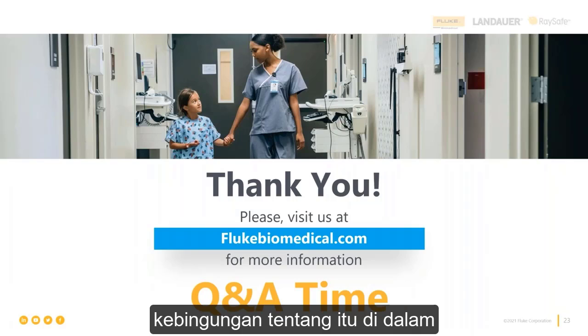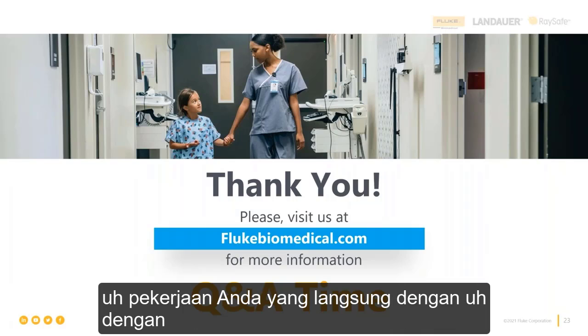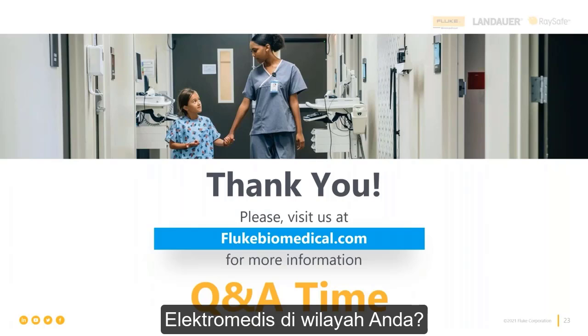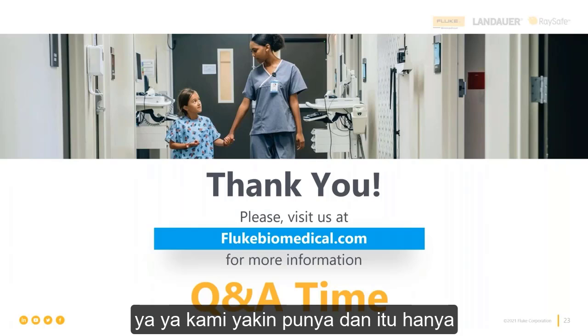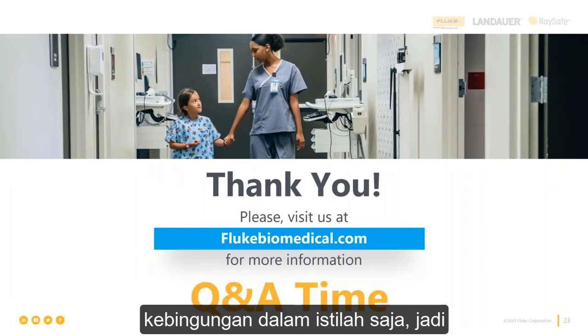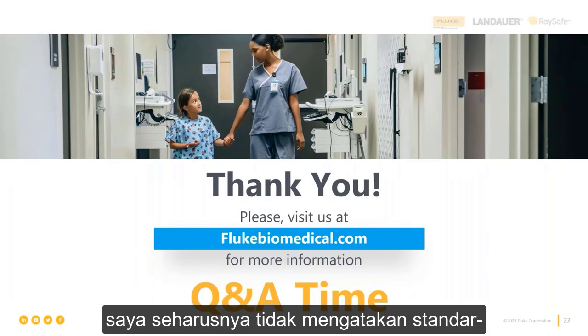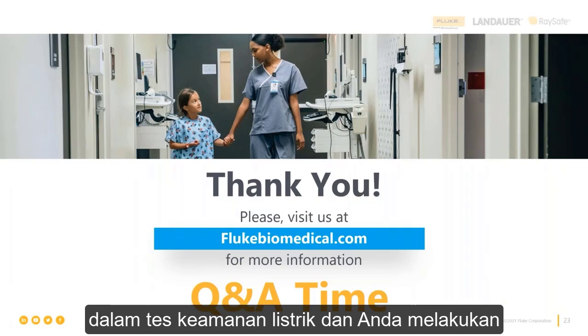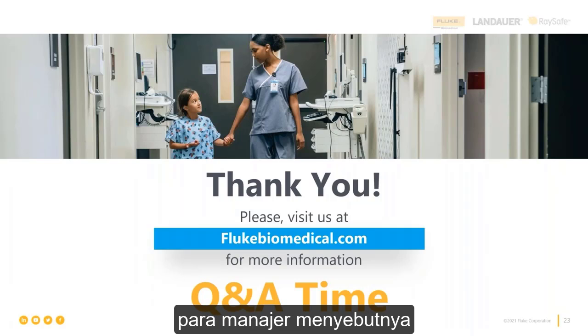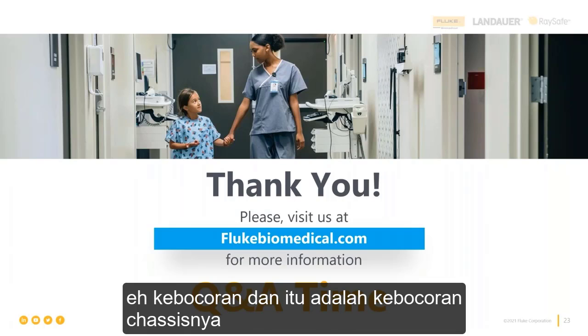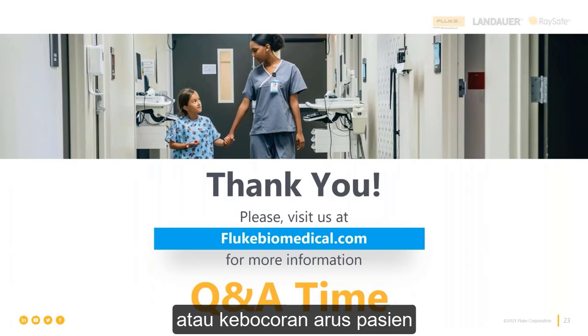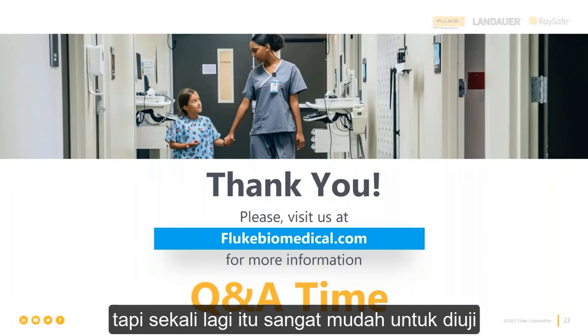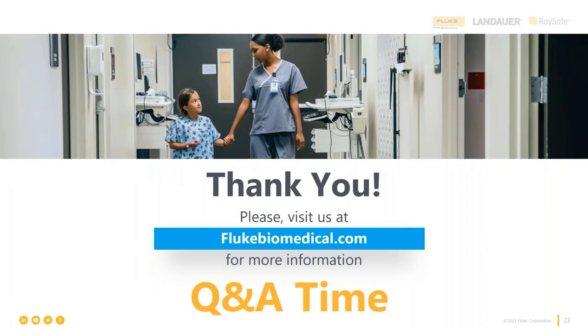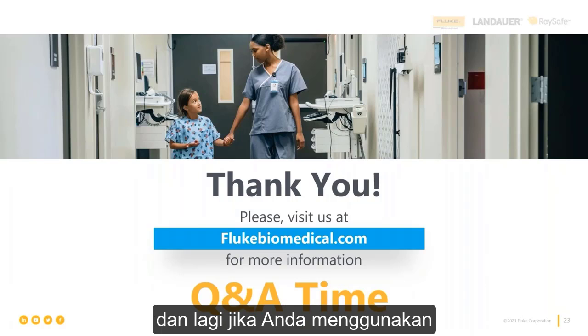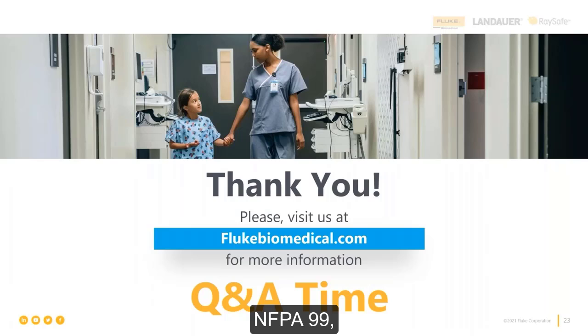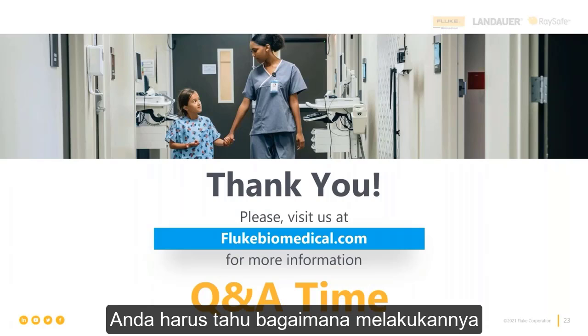Justin, have you run into confusion about that working directly with biomeds in your territory? Yeah, we sure have, and it's mostly just confusion of terms. You have your standard electrical safety test where you're doing ground wire resistance, and some manuals call it low frequency leakage, or chassis leakage, or patient leakage current. But it's really easy to test. Right, it's just your standard electrical safety test, and if you're using NFPA 99, you should know how to do that.